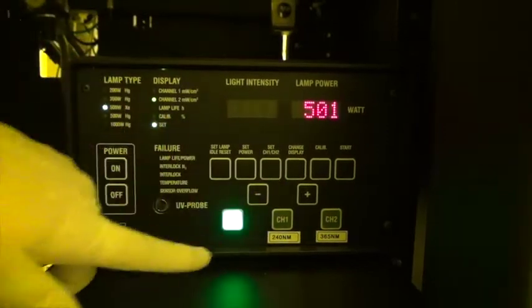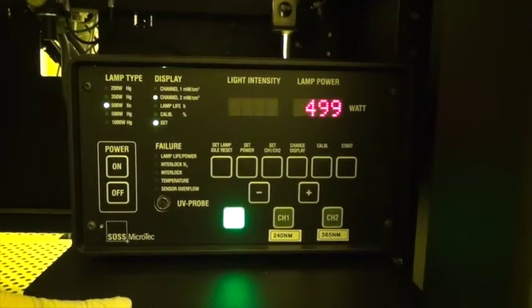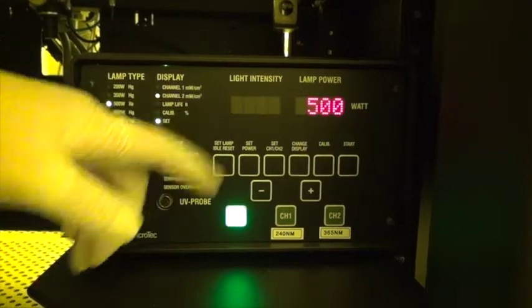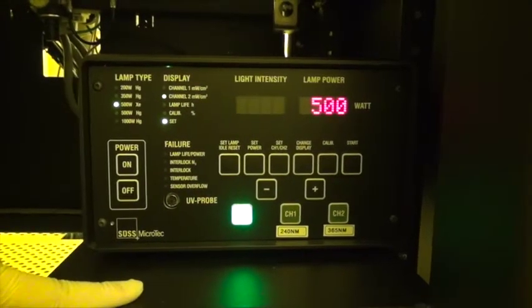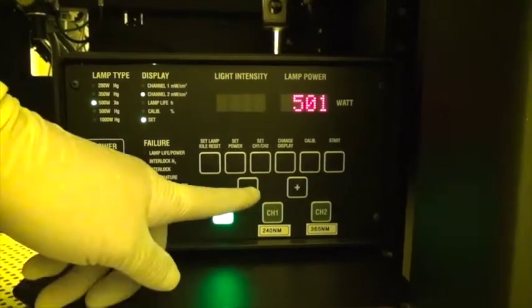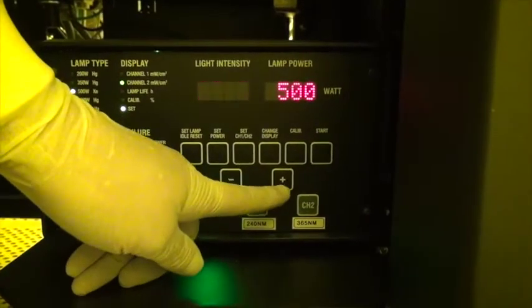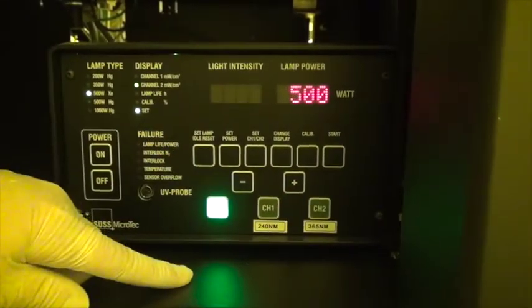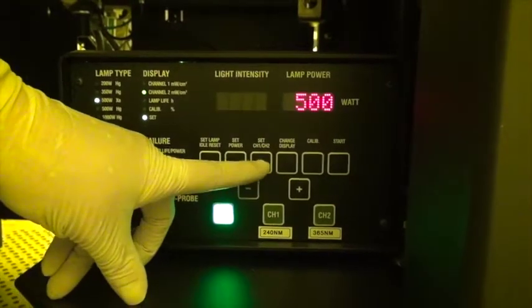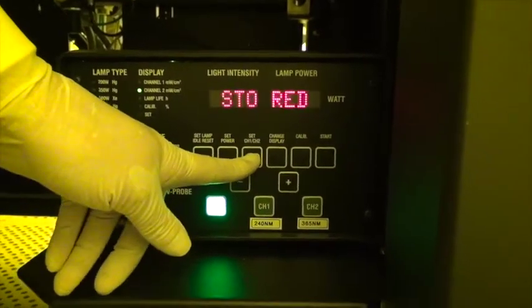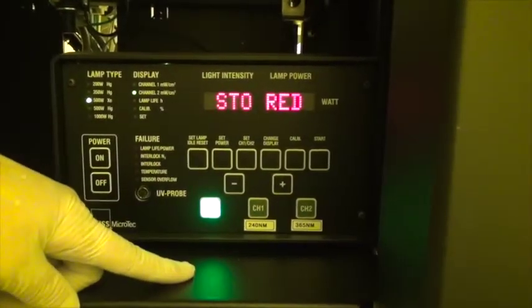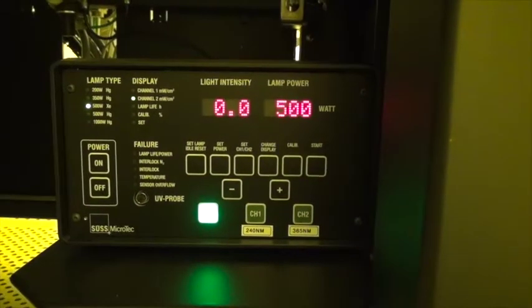Press and hold until the display changes. This now shows the set point for the constant intensity mode. And if we want to change it we simply use the plus and minus buttons here to change it. Once the correct intensity has been set, press and hold again. And now the value is stored.